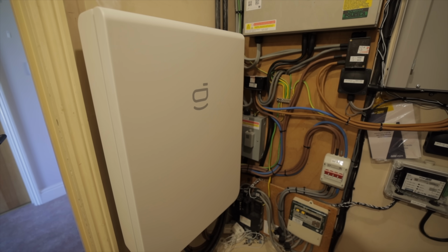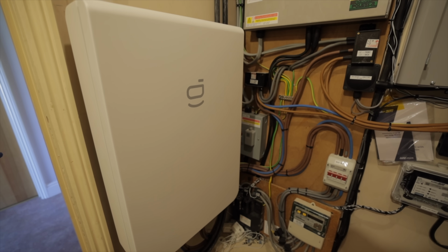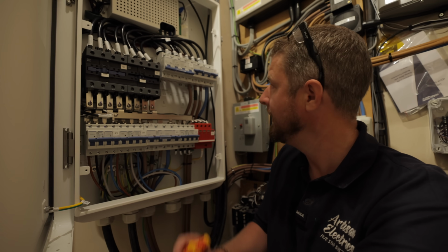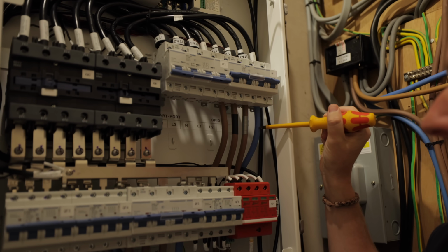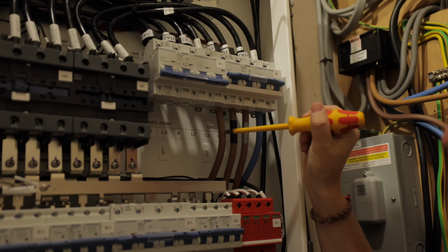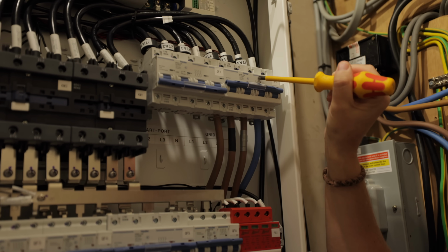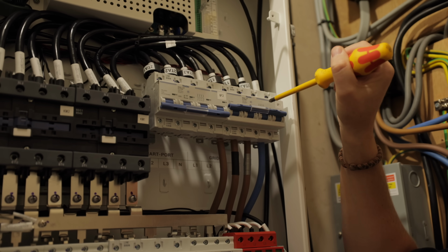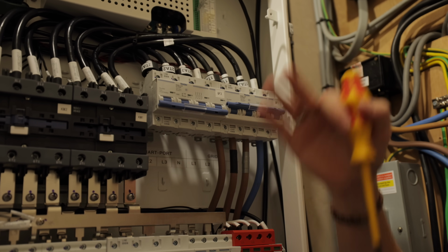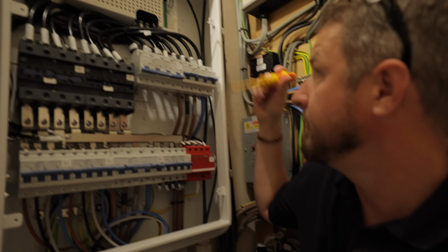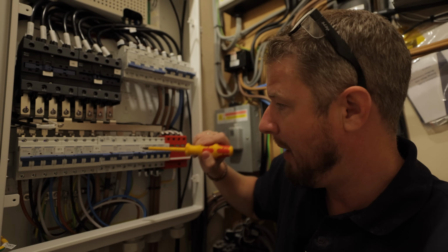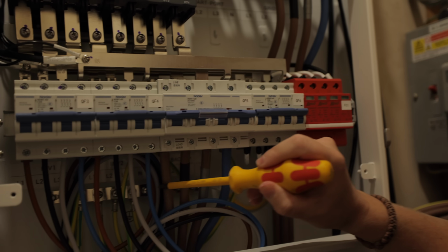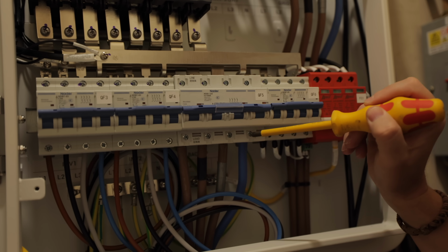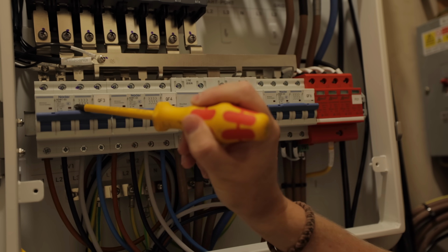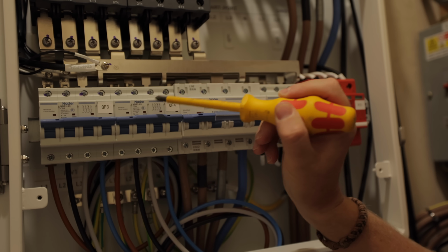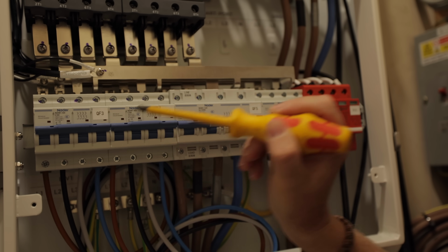So let me explain how this gateway works, because you might wonder how it manages on-grid and off-grid and stuff like that. Basically your main power from the street, the main incoming supply to the property, feeds into here. This is a 100 amp MCCB, 4-pole. So if you isolate that, all power goes off to this gateway. But then the outgoing power to the house, so all of the circuits you want to be backed up, come off of this 100 amp breaker. Here you have your two breakers for your two inverters. Now we've only got one in at the moment, but we've wired up both.